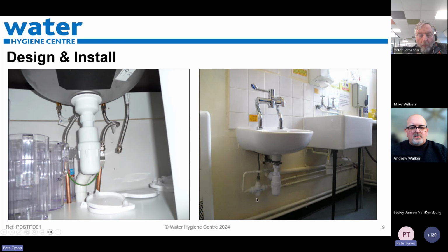Also on the right hand side here, we have a thermostatic mixing tap being supplied by a thermostatic mixing valve. When this new tap was installed, the person doing the installation should have identified that the valve was no longer needed and should have been removed. What we're doing now is giving bacteria a location to form, which is then supplying water at 38 to 42-43 degrees centigrade. Legionella proliferates quickest at around 37 degrees, closest to body temperature, and that's not too far away from the temperature in this system feeding the hot tap. So this really is a location where things could occur that we don't want.